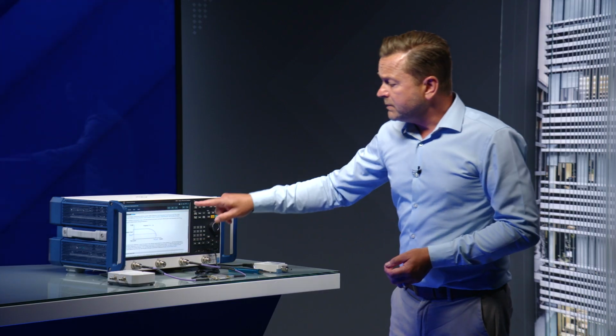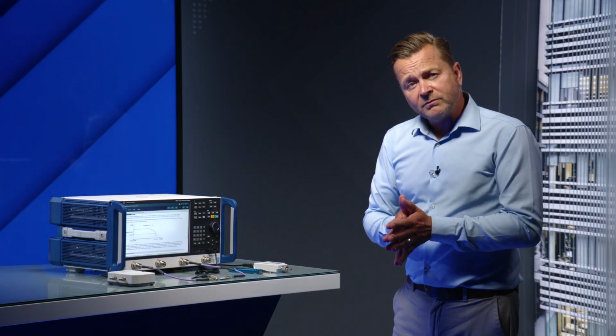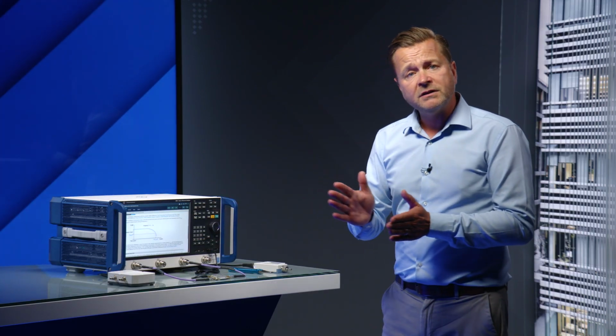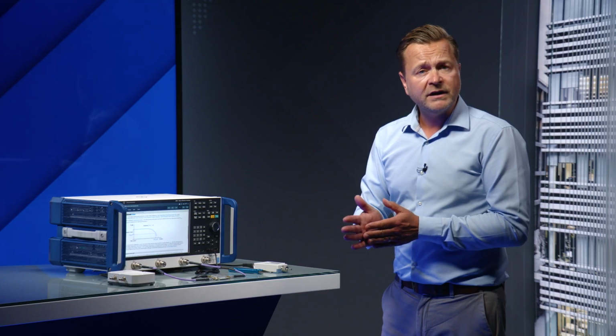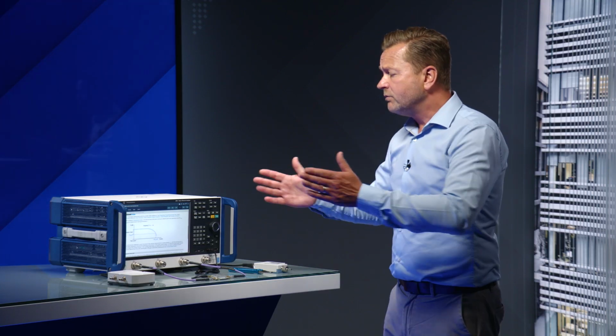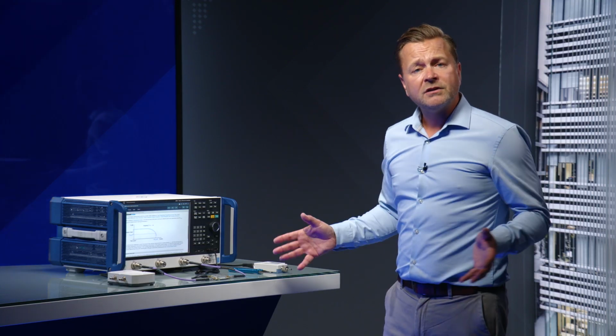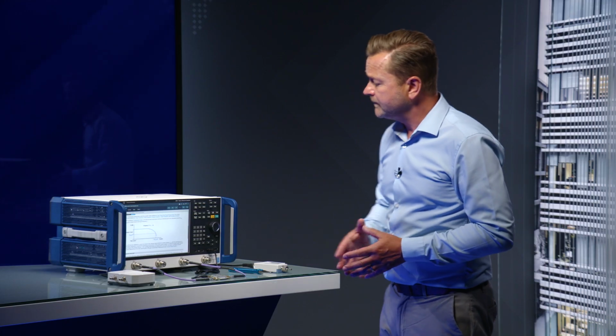The ZNB3000 will automate this measurement, so it makes that swept measurement and establishes the compression point for every frequency point across the axis. So we get a swept compression point measurement across frequency.